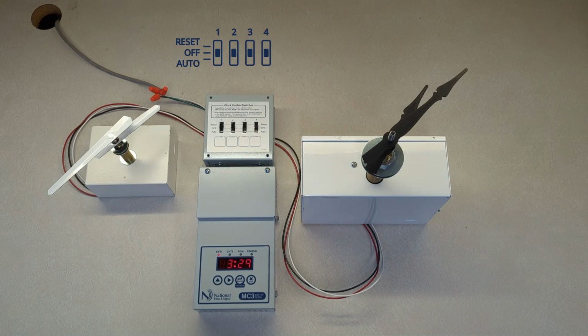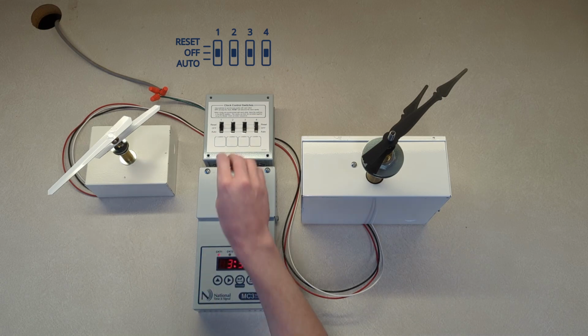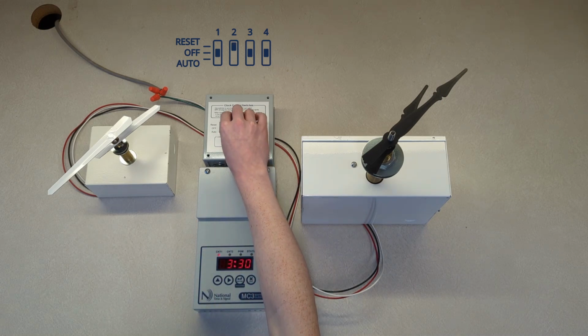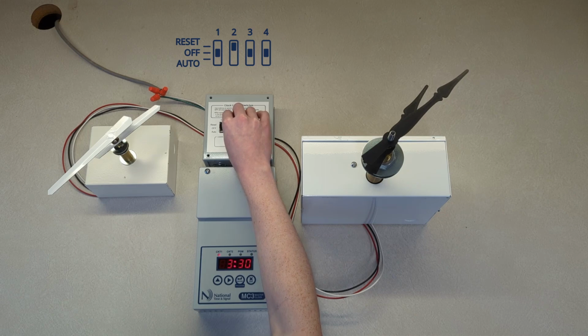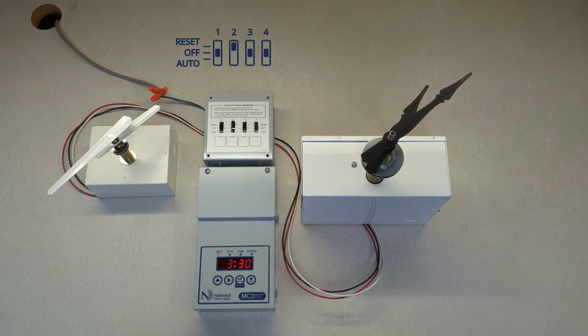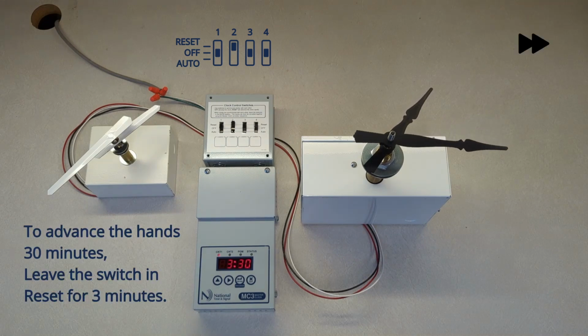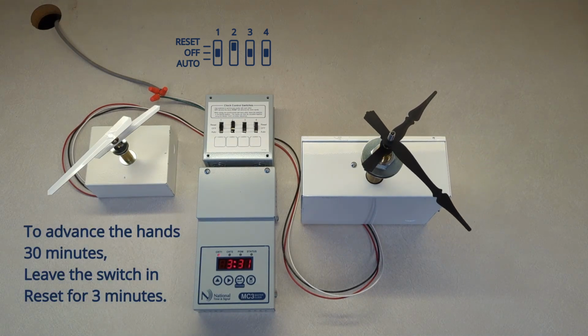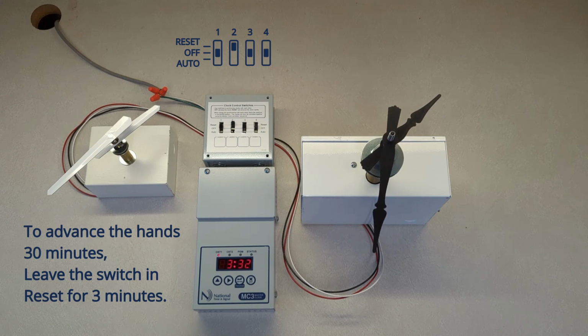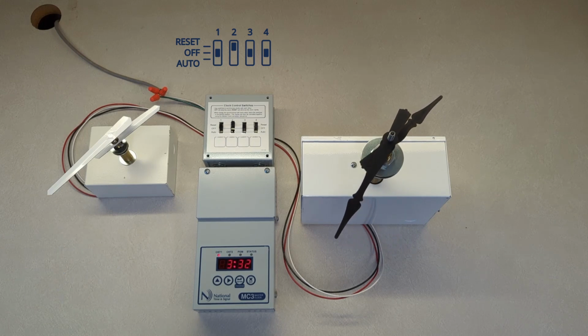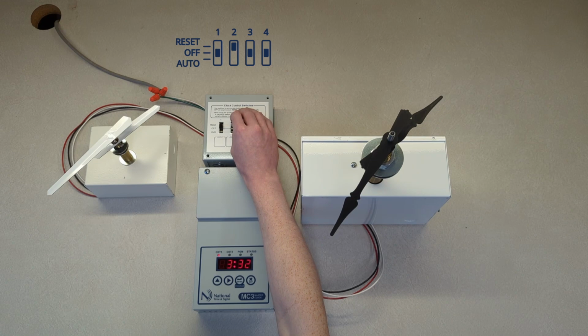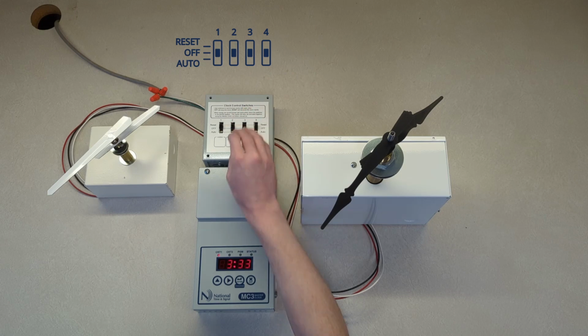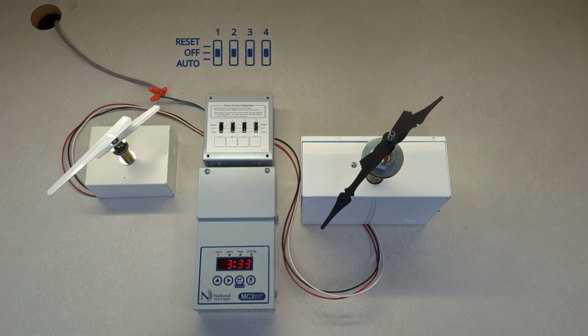Clock 2 is on the right and it is currently behind clock 1, so slide switch 2 up to the reset position. This will advance clock 2 at 10 times speed. Slide switch 2 back to off when the position of clock 2 matches clock 1. Use the other switches to synchronize any other secondary clocks you may have.